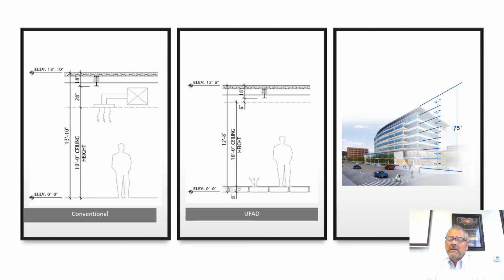The other thing that might not seem obvious at first is you can make the building actually shorter. By putting the ductwork in the floor and using the floor as a plenum, instead of having ductwork in the ceiling, you can actually lower the ceiling height quite a bit and still have 10 foot within the occupied space. So a lot of people think, oh, I don't want underfloor, my building's going to get too big. It actually makes your building smaller.